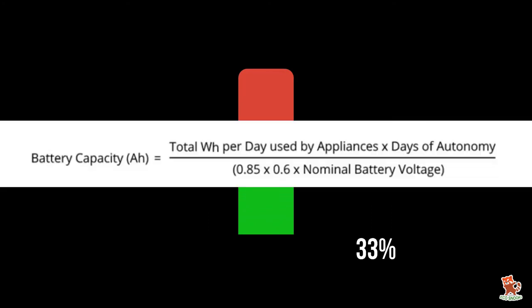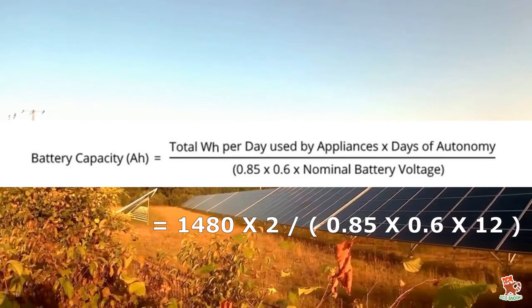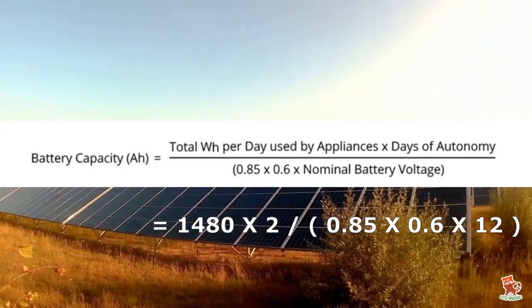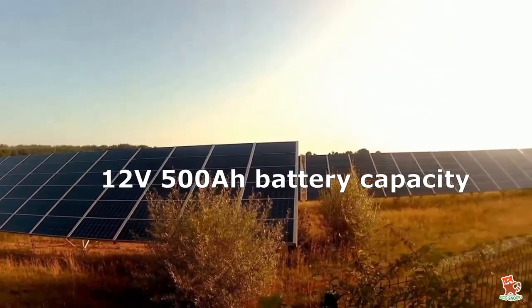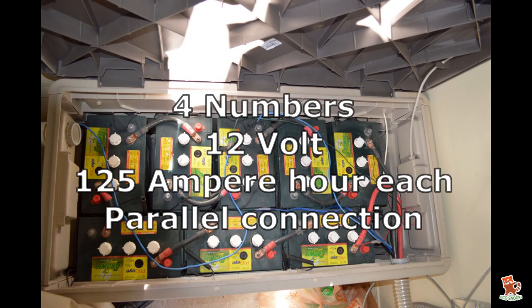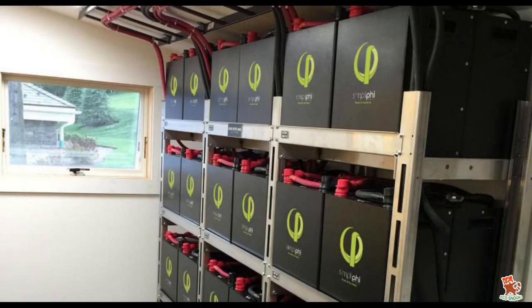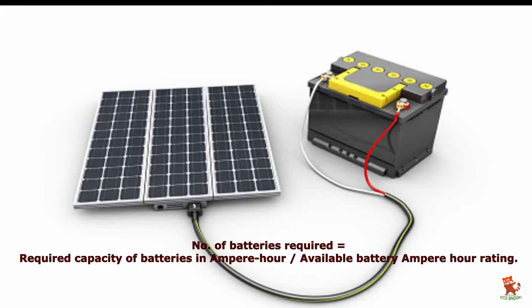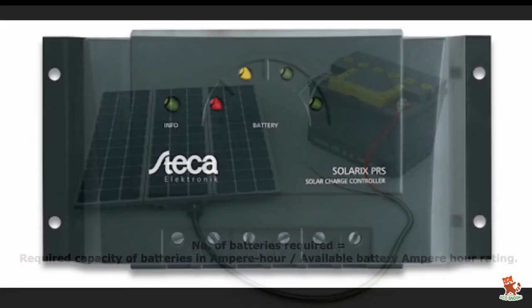Now find the size, rating, and number of batteries. We use the battery capacity formula in ampere-hours. Days of autonomy means the backup days required by the battery — here we consider two days. The nominal voltage of the deep cycle battery equals 12 volts. The required capacity of batteries equals 483.6 ampere-hours. We therefore need a 12-volt, 500 ampere-hour battery capacity for two days of autonomy. We may use four batteries each of 12 volt, 125 ampere-hour connected in parallel. If the available battery capacity is 175 ampere-hour at 12 volts, we may use three batteries. You can get the exact number of batteries by dividing the required capacity by the available battery ampere-hour rating.